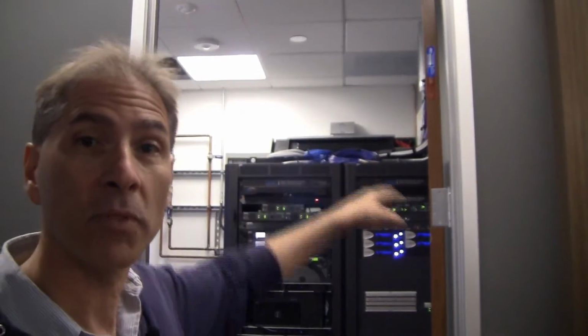Right back there is the Liebert DataMate. It's rated at 20,000 BTUs, so it's about 1.75 tons of capacity. And what's happening is that the compressor is on and the room temperature is absolutely freezing. So our job is going to be to troubleshoot this unit to figure out what is wrong, what we need to fix in this scenario. So let's get to it.